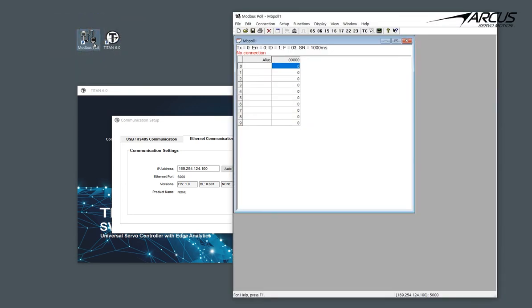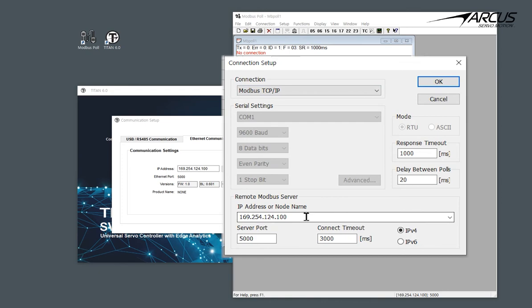Go to the Communication menu and select Connect. Select Modbus TCP/IP. Here the IP address should be the same as the one that we set up on the Titan controller and the communication port should be set to 5000.